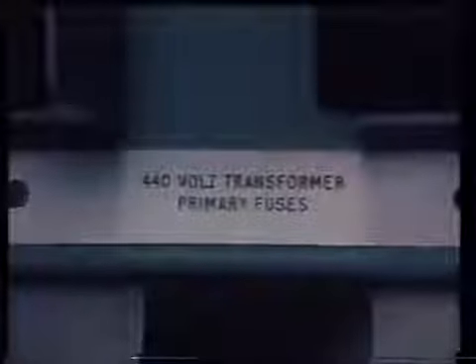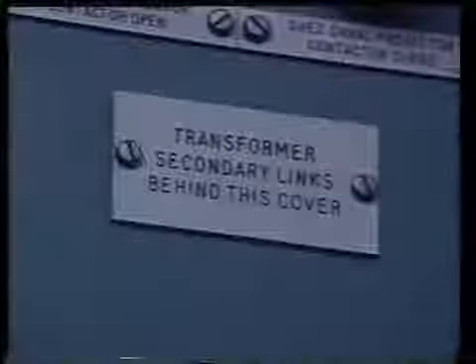The lighting circuit on board ship is usually 220-volt or 110-volt AC supply, provided by a set of step-down transformers connected in delta-delta. On the rare occasion when one of the 3 single-phase transformer units may develop a fault, it can be disconnected by first removing these primary fuses, then removing the secondary links of the phase affected.